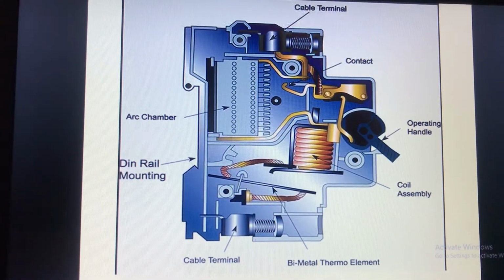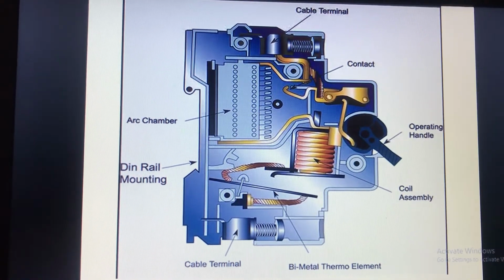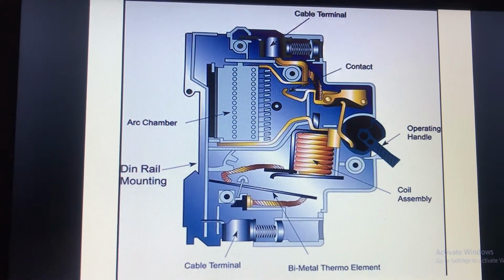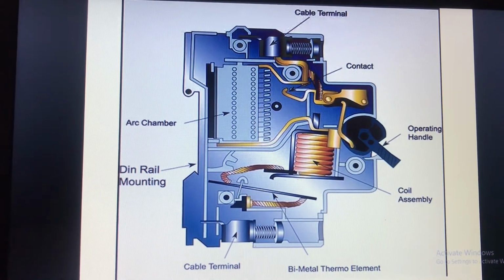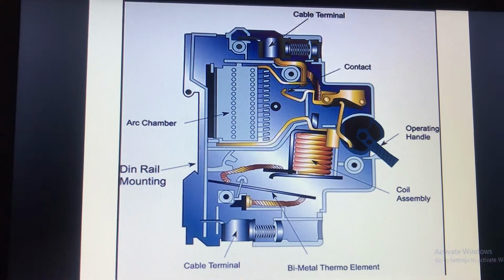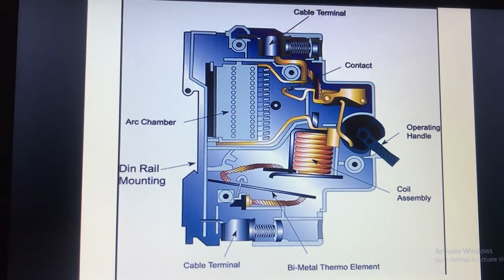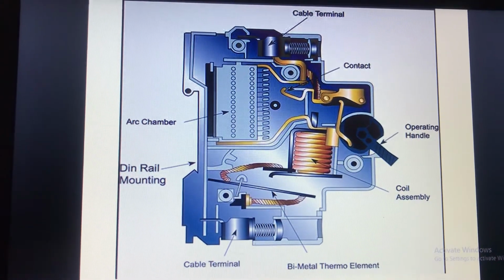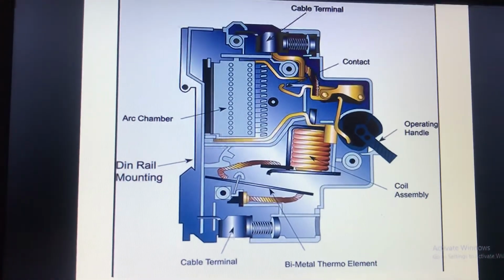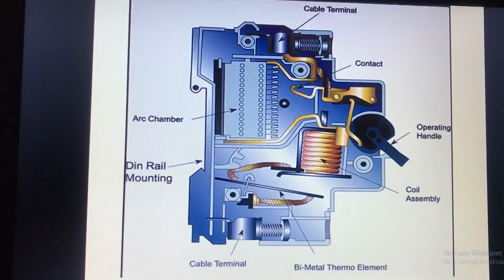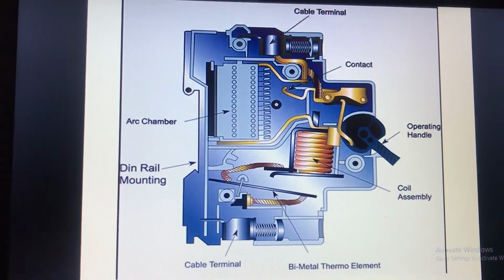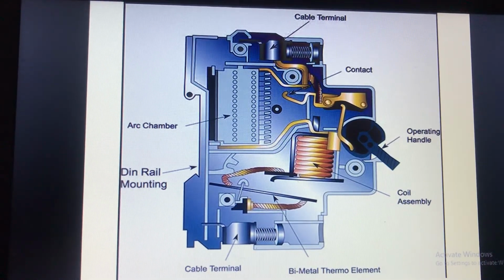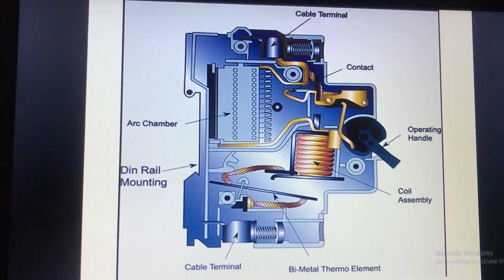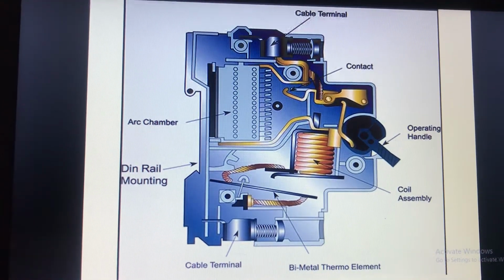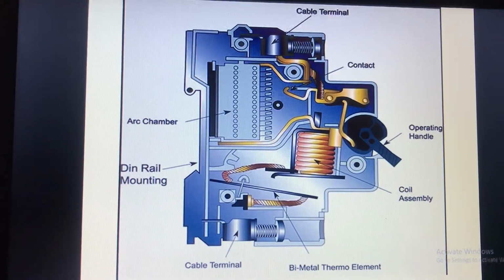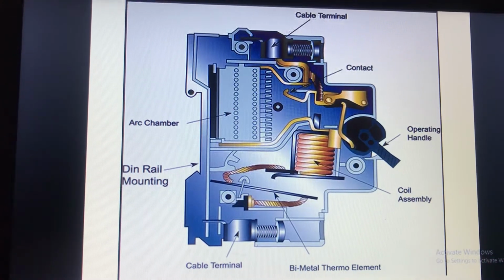Then is the arc chamber. Arc chamber, it basically provides the arc extinction. So when the contacts get opened, there is the arc between those contacts. So by this arc chamber, the lengthening of the arc occurs. As R is directly proportional to L, when the lengthening of the arc occurs, the resistance increases and the voltage drop also increases, and the system voltage can't maintain this voltage drop. So finally the arc will get extinguished. So this is the diagram for an MCB. These are some basic parts.